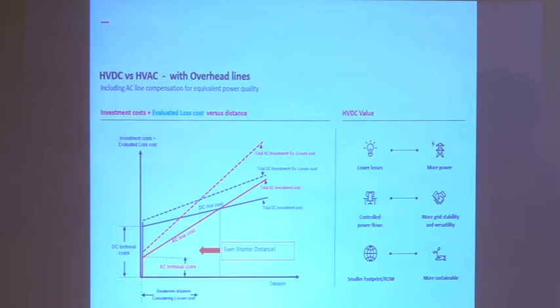the cable break-even distance for HVDC is very low—only 80 kilometers—because of the cable's nature; it cannot carry capacitance and AC power well. So the break-even distance is only 80 kilometers. So if we are to connect two places with a high megawatt interconnector, we can think of DC even if the distance is just 80 kilometers. So these are the first triggers, and of course there would be some technical benefits which we touched on a little earlier.